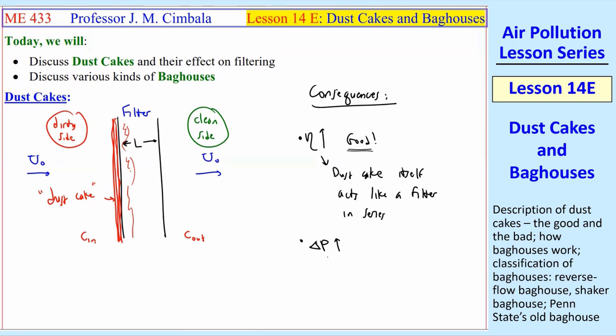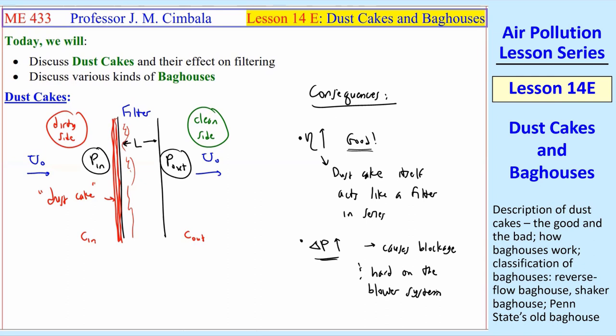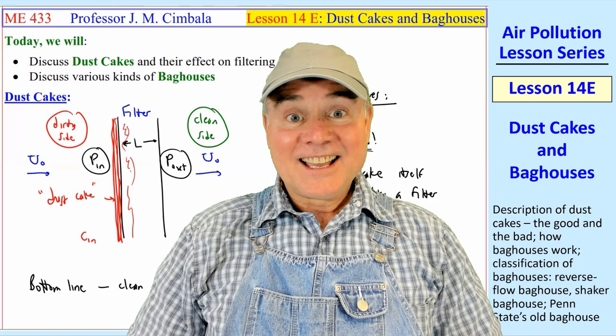Well, the bad news is that delta P also goes up. If we call P-in the pressure upstream and P-out the pressure downstream of the filter, this dust cake can really increase that delta P. That causes blockage, and it's hard on the blower system in your ducts and things like that.